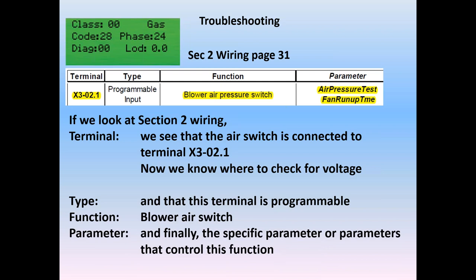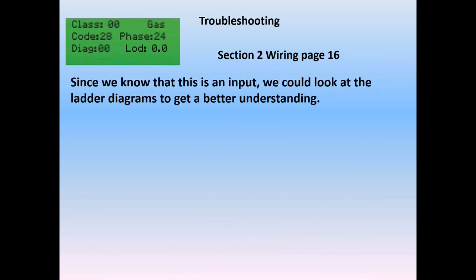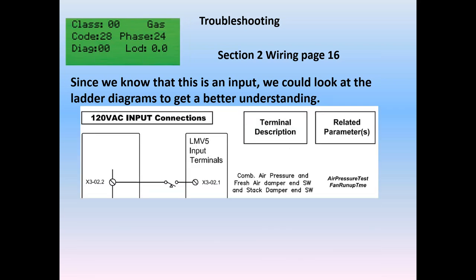We know the parameters that control this terminal — in this case, two parameters: air pressure test and fan run-up time. Air pressure test will activate or deactivate the input; fan run-up time will set the amount of time we get to make the air pressure once the fan is started. Also in the wiring section, since we know this is an input, we can look at the ladder diagrams for a better understanding. We go to the 120-volt input, section 2, page 16, and we see that the combustion air pressure switch is in fact connected to X302.1, controlled by the parameters air pressure test and fan run-up time. All through the tech support manual, we constantly tell you the terminal number, the function, and the related parameters — covered in the wiring chart, parameter programming, diagnostics, and troubleshooting.